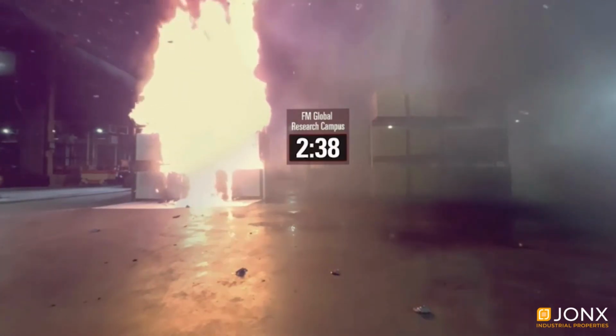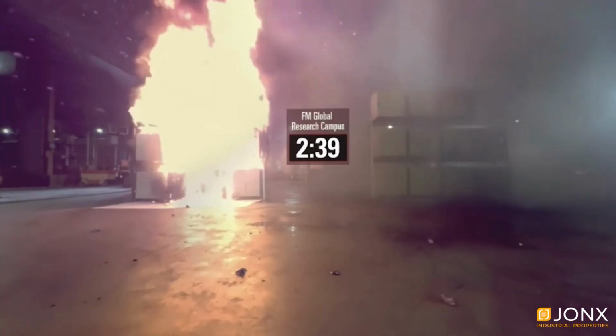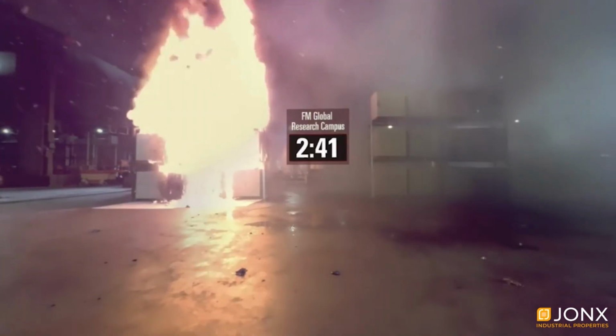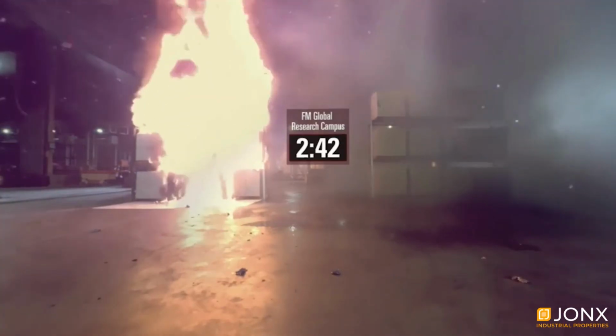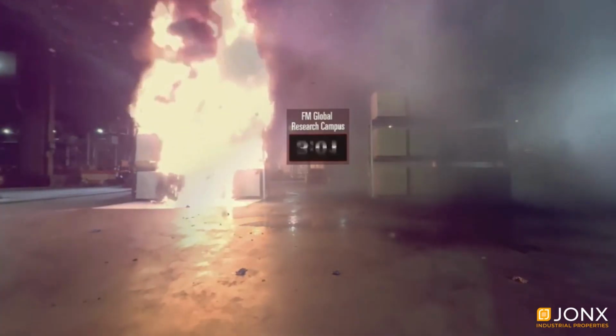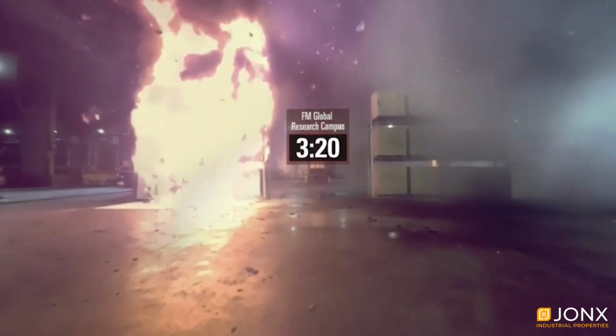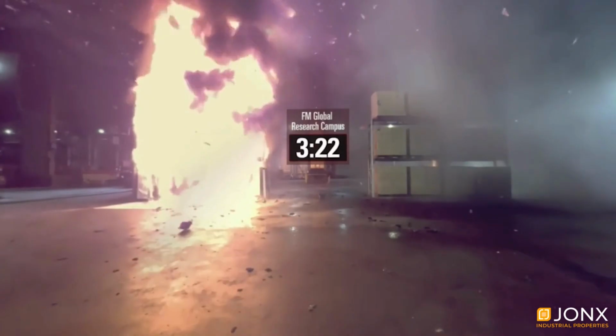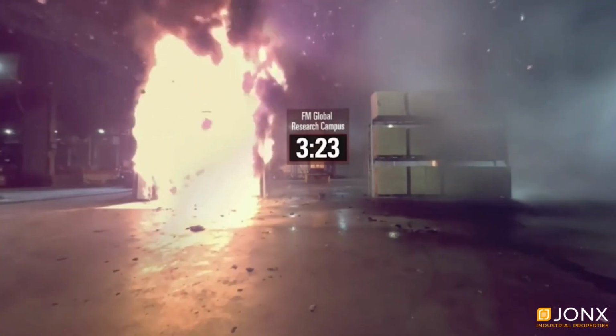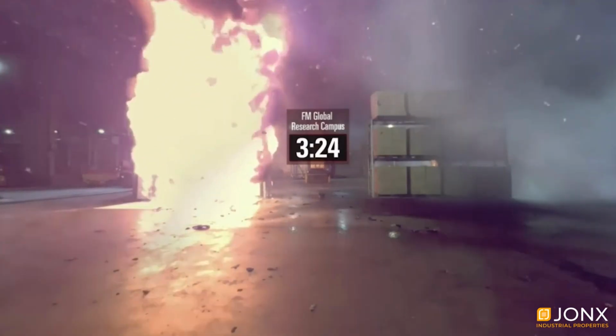100%. At 538 degrees Celsius, that's enough to weaken structural steel and collapse your building. The fire on the right is completely controlled, and on the left you can see the fire still building - that's a topic we'll cover now: the difference between control mode sprinklers and ESFR.